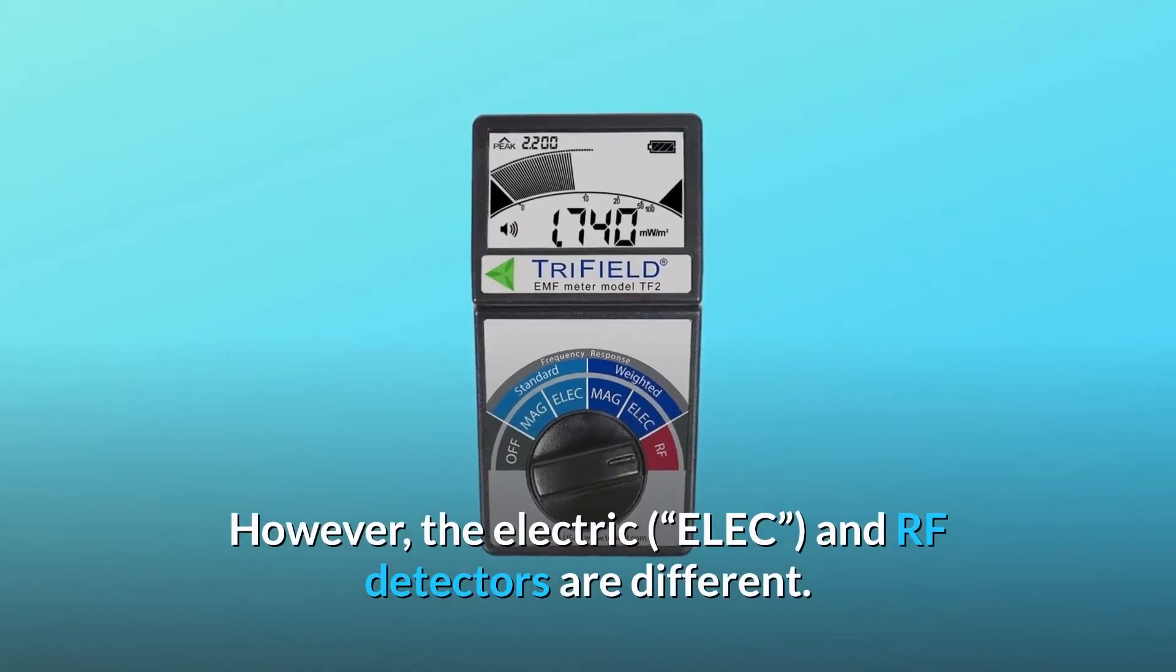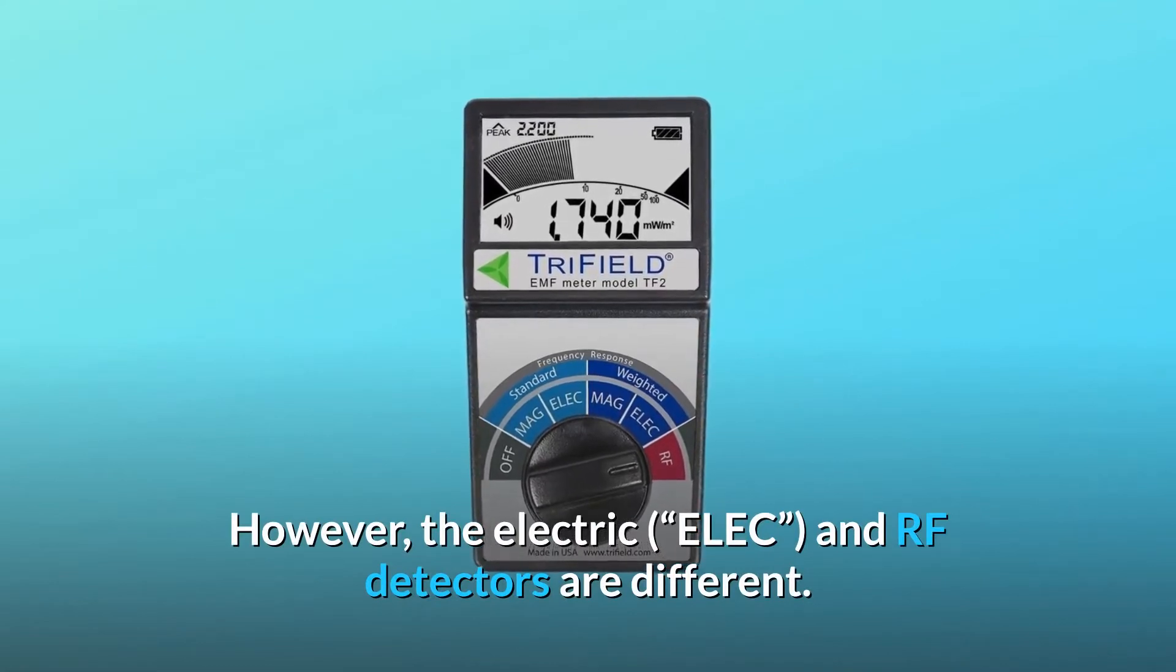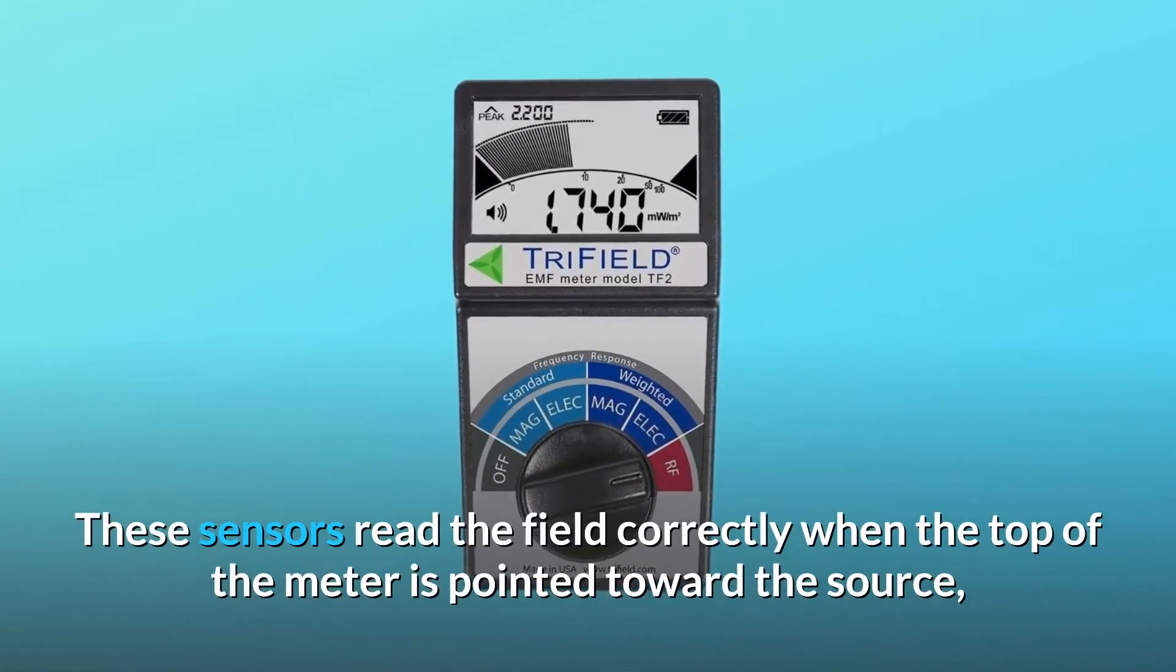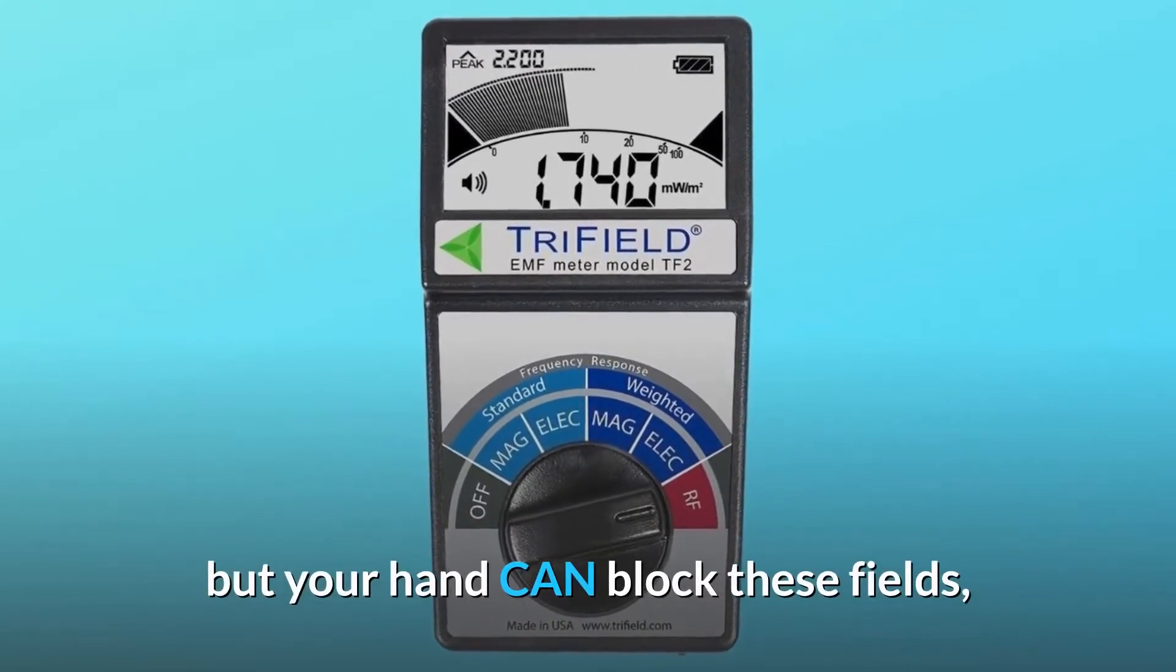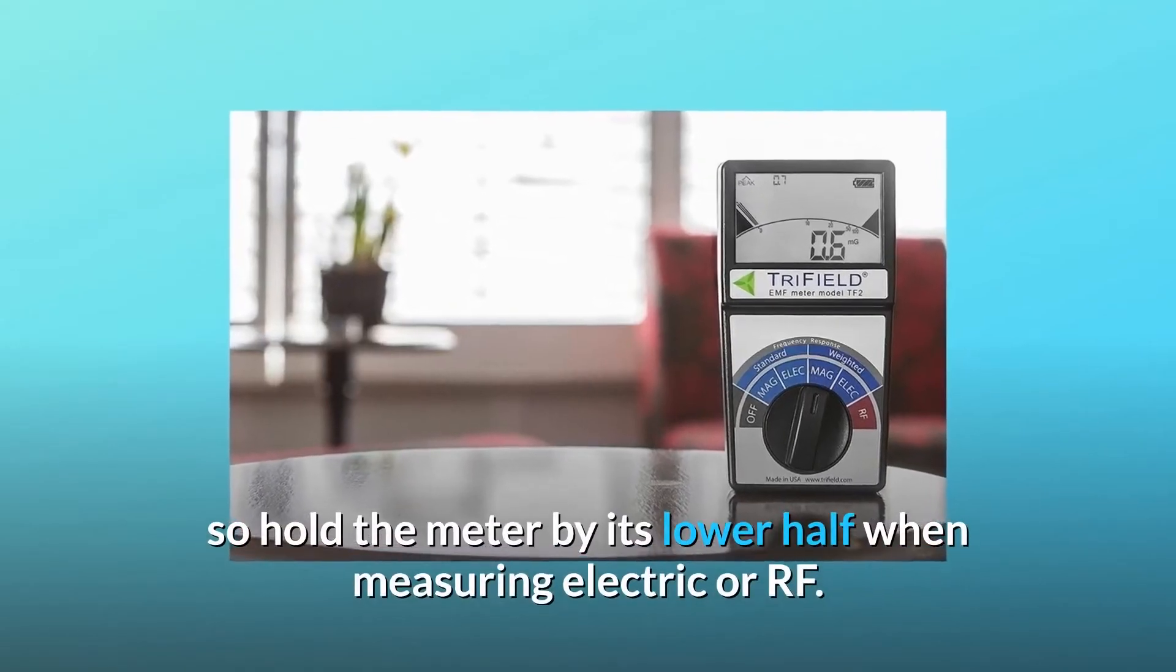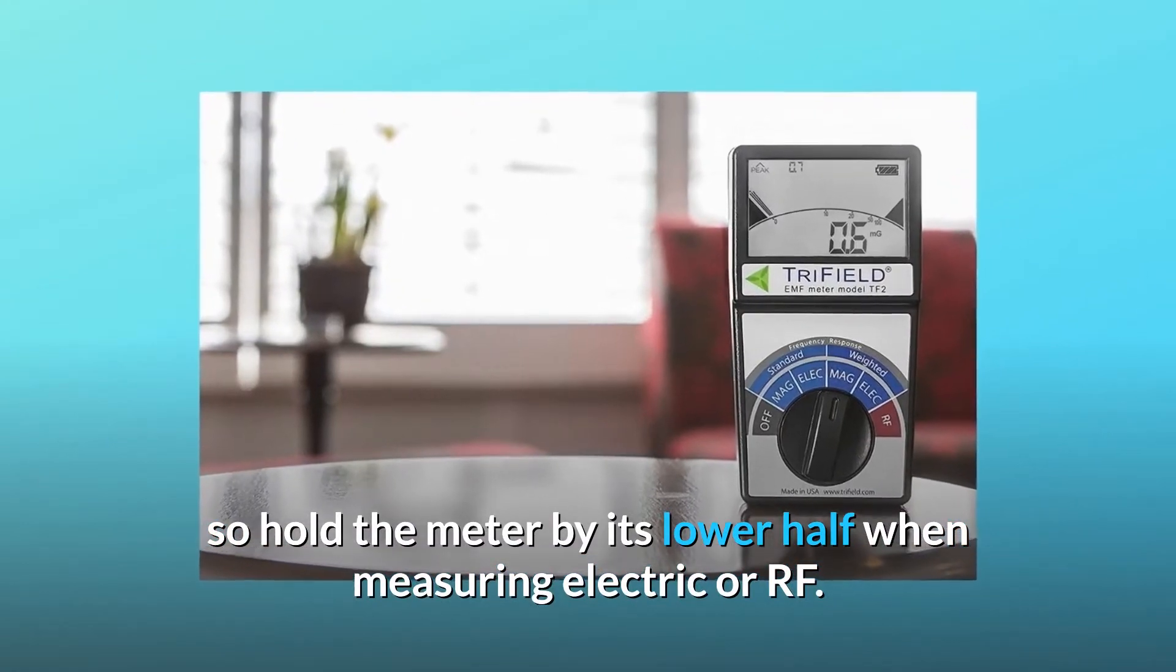However, the electric (ELEC) and RF detectors are different. These sensors read the field correctly when the top of the meter is pointed toward the source, but your hand can block these fields, so hold the meter by its lower half when measuring electric or RF.